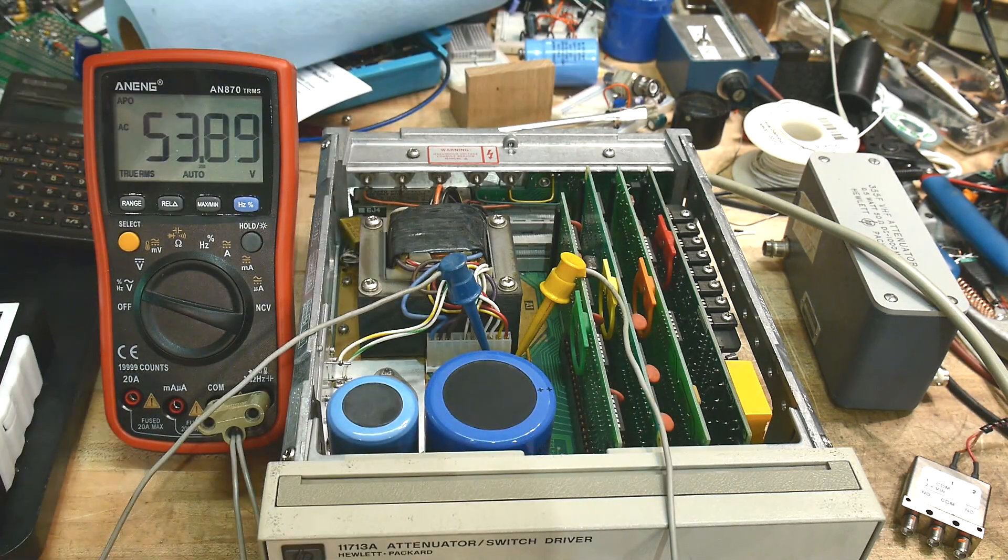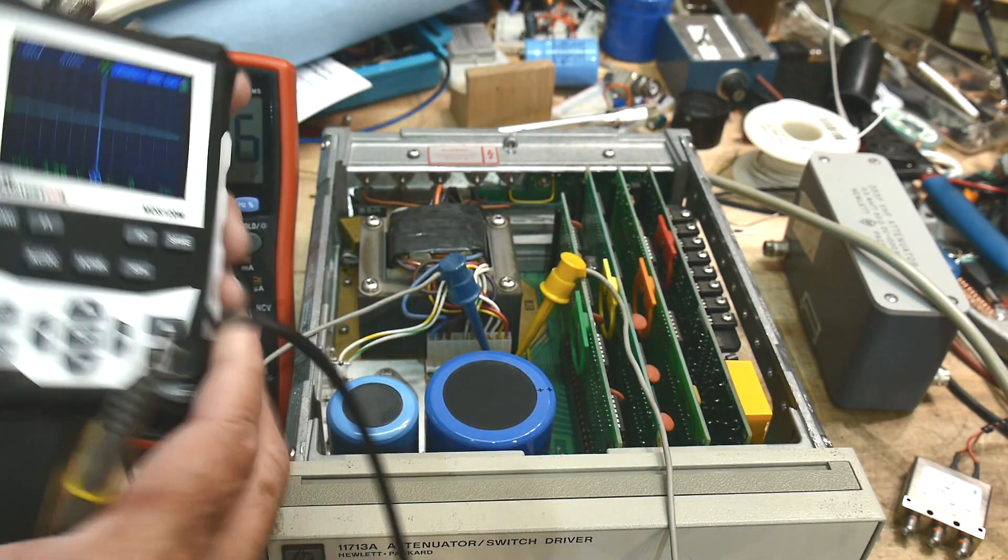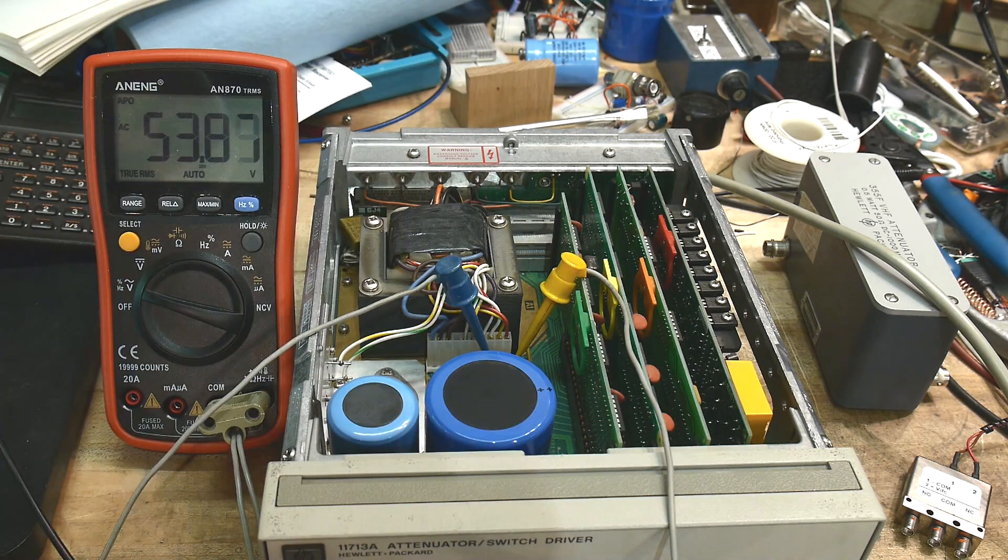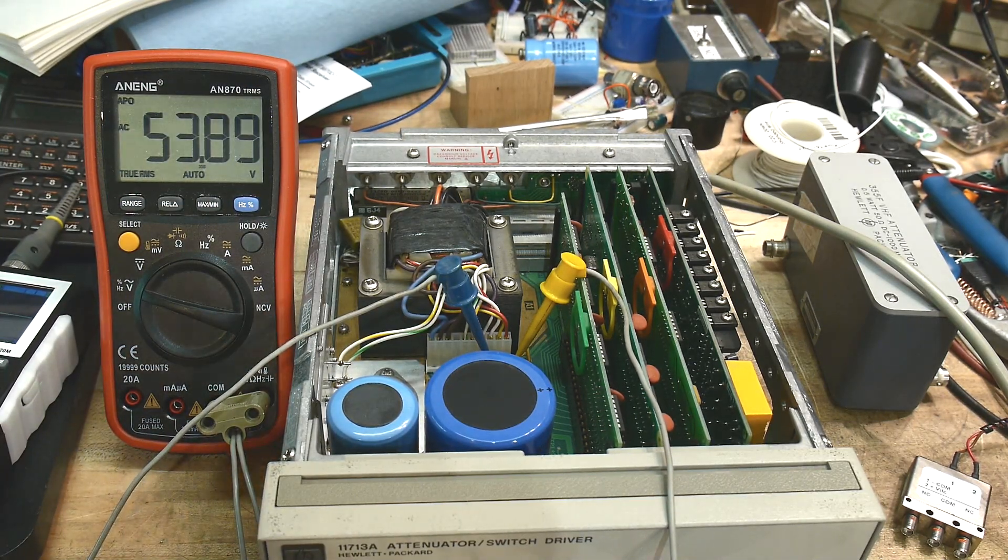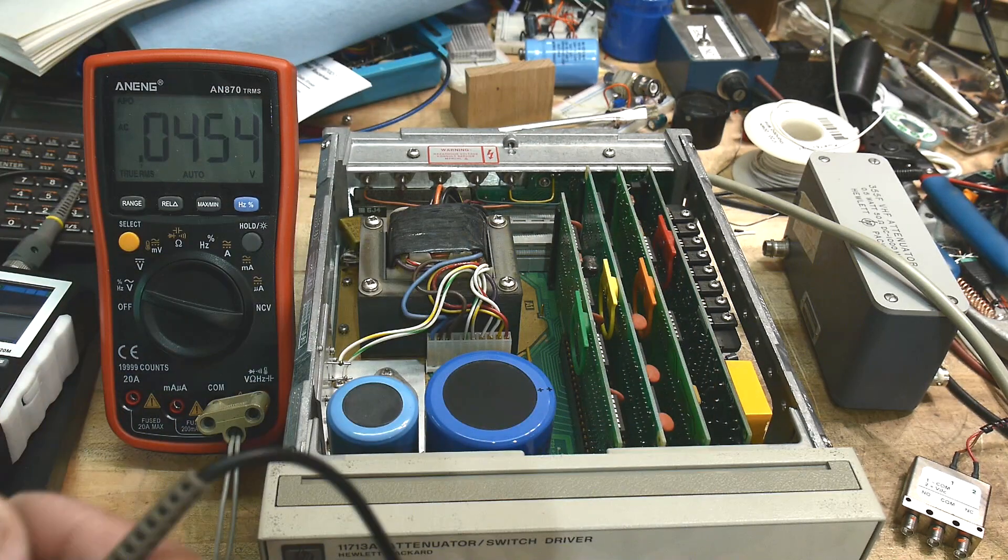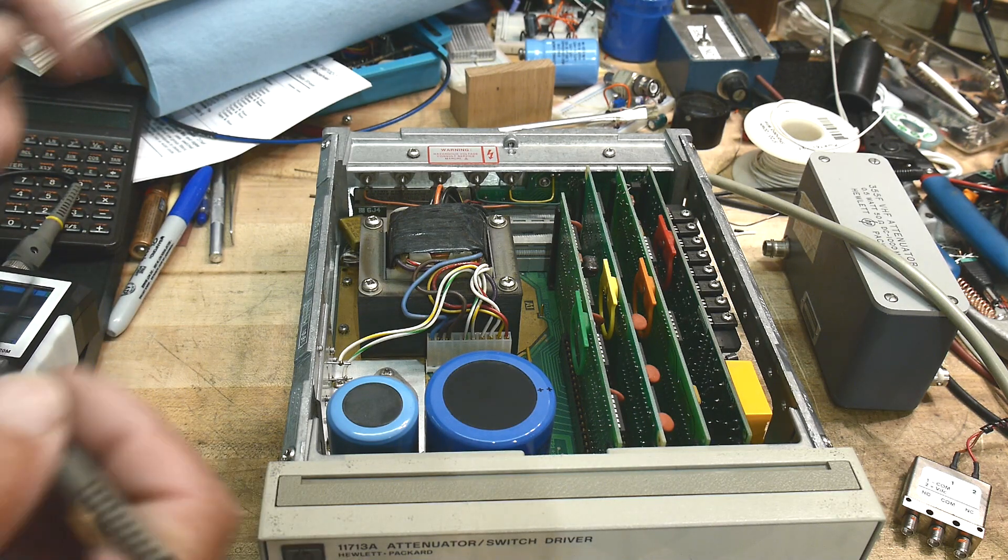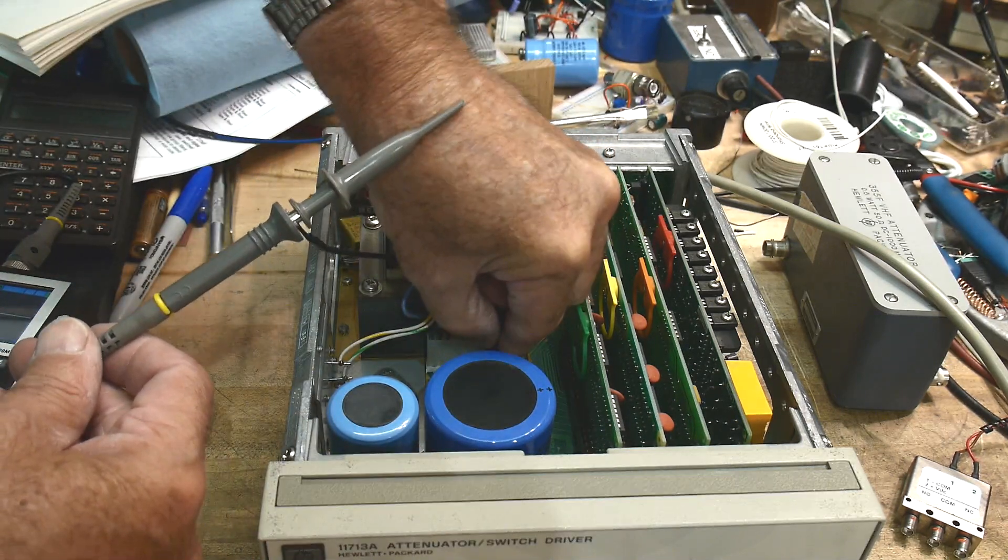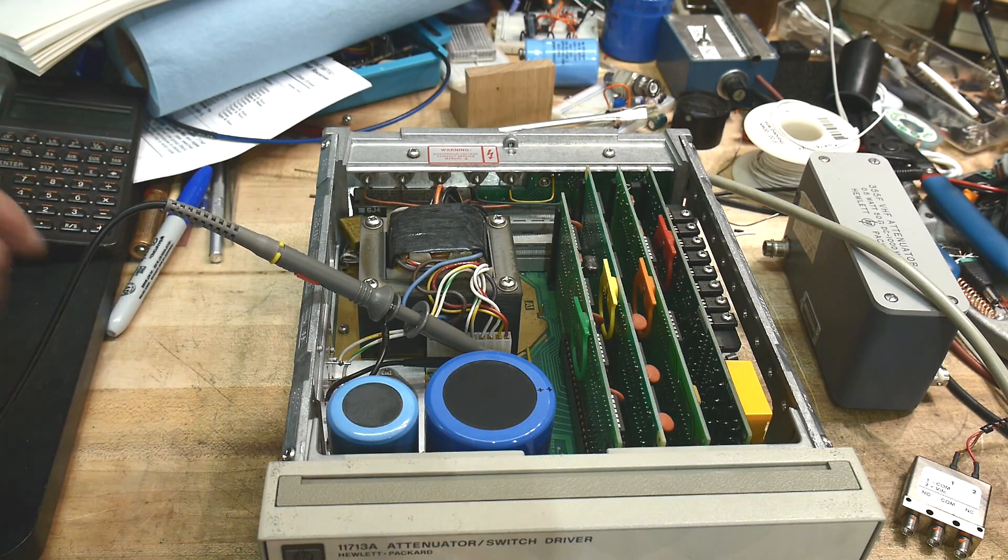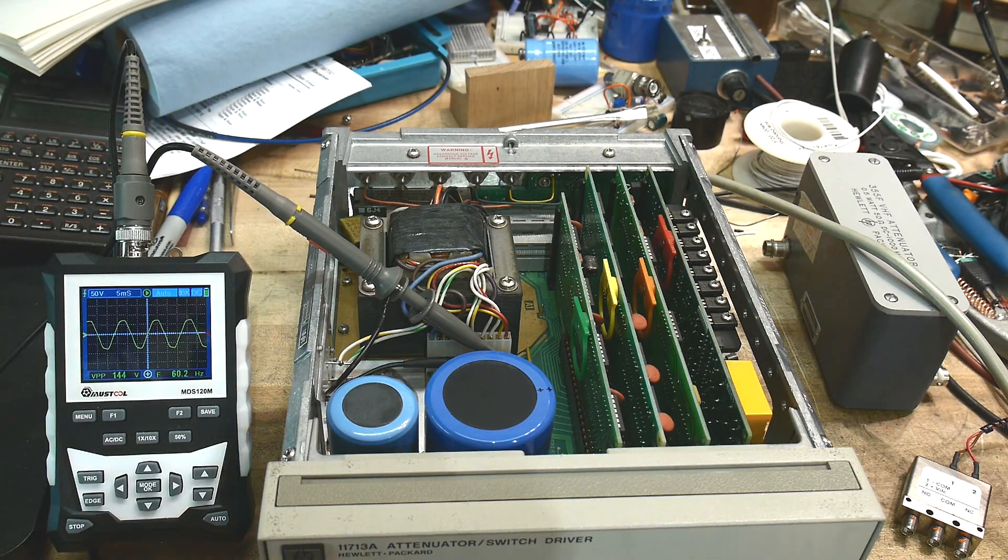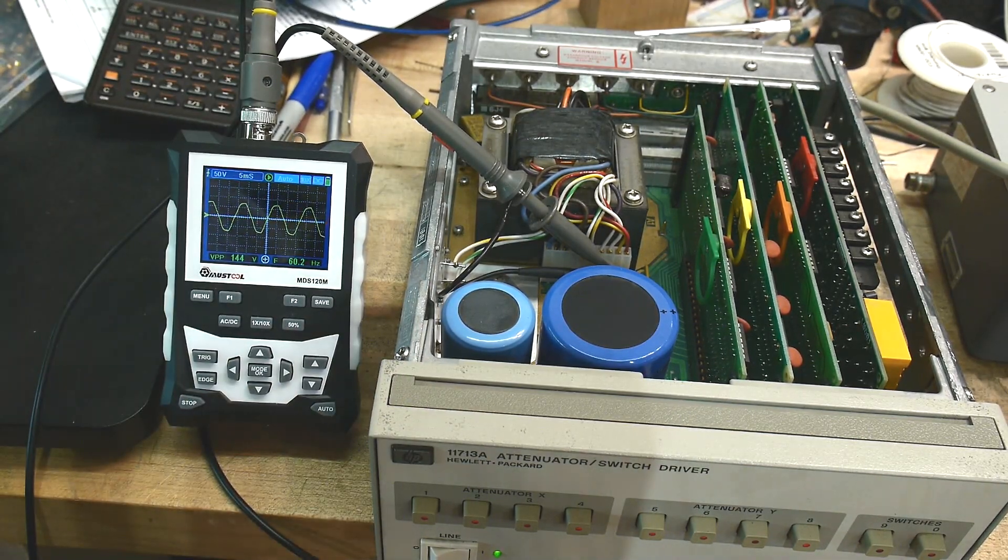I have this little portable oscilloscope that is completely no earth ground, it's completely floating, it's battery powered. Which means that this probe, I can do anything I want with it, which is great. So this is a great application for this scope. Let's put it on this 53 volt RMS side. Now I can reach my scope in and I can tie it to ground. It's not earth ground, it's just ground, but they're both sides are floating. So now we can look at that waveform and we're under no penalty of grounds.